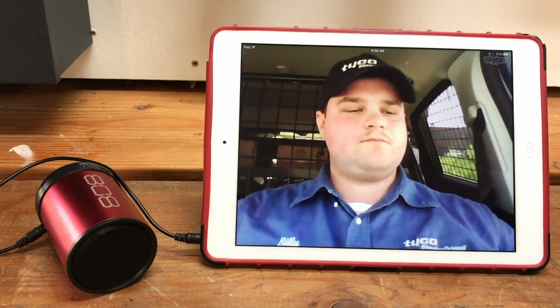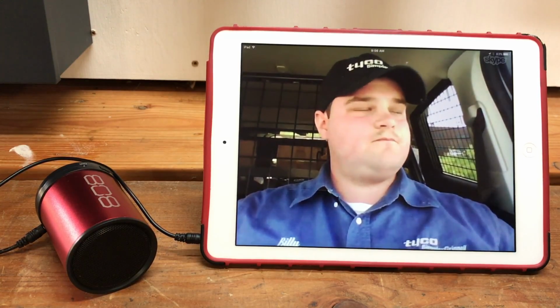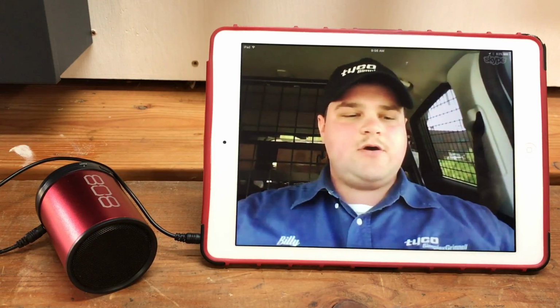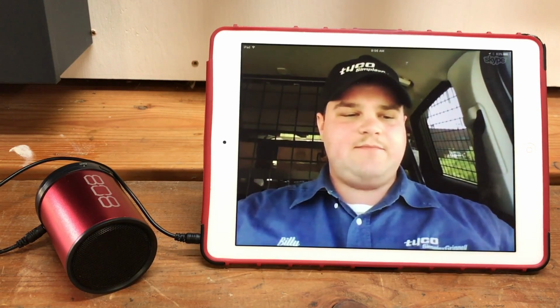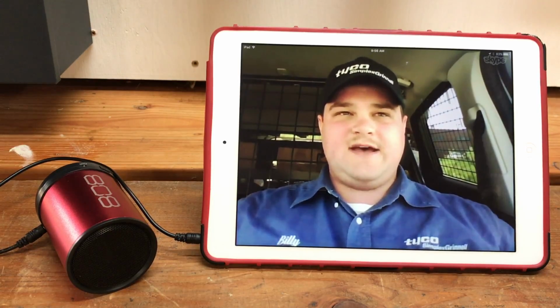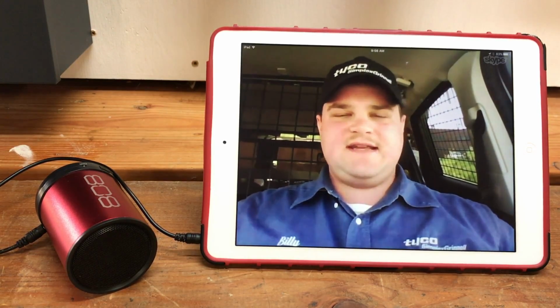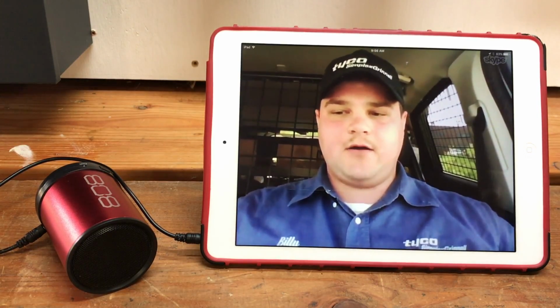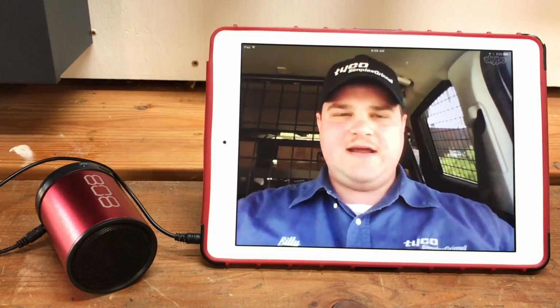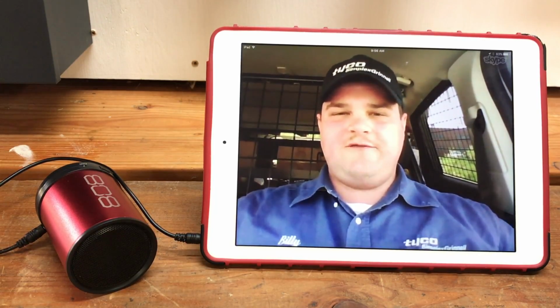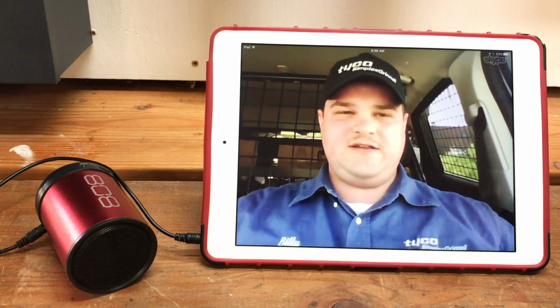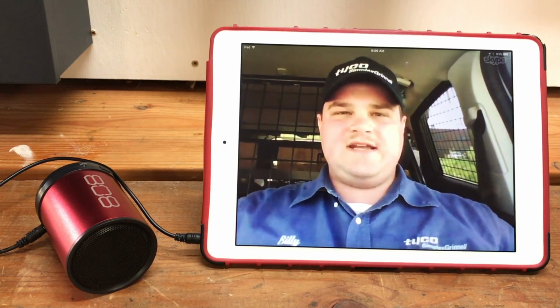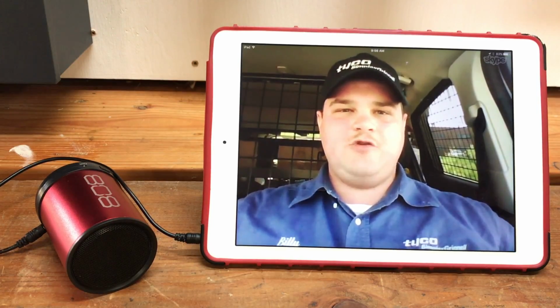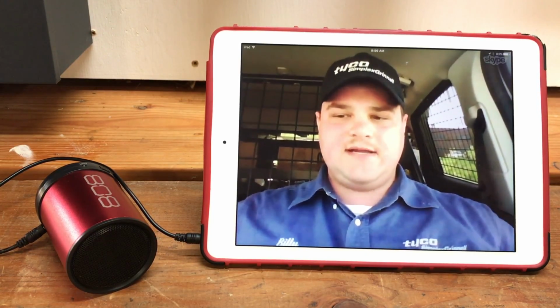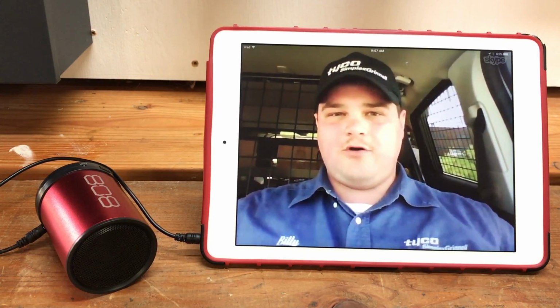Alright, let's get started. So the first question we got is, why do people put supervisories on sprinkler systems in buildings? What a supervisory is, it's basically a monitor point on a sprinkler system. Sprinkler systems have water flow switches and tamper switches as part of the interface device on a fire alarm. What the supervisory is going to monitor is the tamper switch, which is basically a control valve on the sprinkler that can cut off the water to any certain point on the sprinkler system. And if that water's cut off anywhere on the sprinkler, you want some type of notification at the panel that's going to tell you exactly where you're not having any water flow.